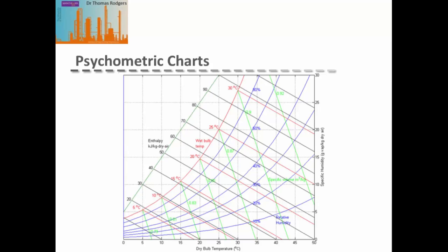Most of these parameters can be read off psychometric charts. Given a dry bulb temperature and a wet bulb temperature, you find the x-axis for the dry bulb temperature and the red lines for the wet bulb temperature. At the corresponding point, you can read off: the specific humidity from the y-axis, the relative humidity from the blue lines, the specific volume from the green lines, and the enthalpy from the dark green lines.